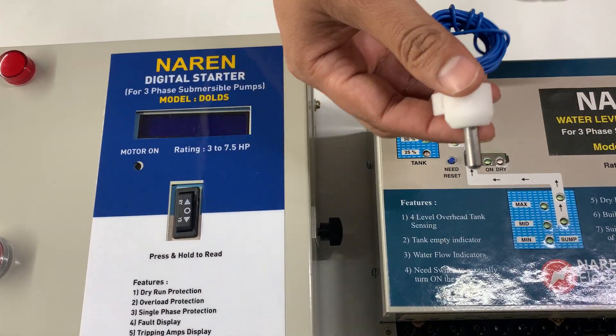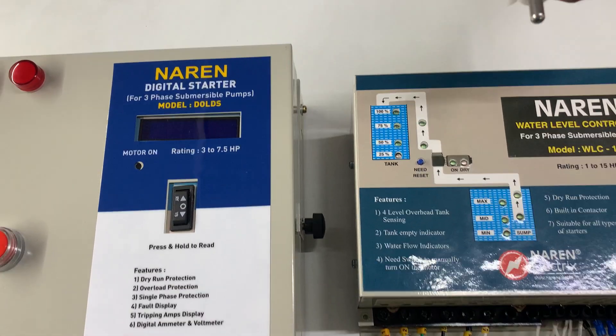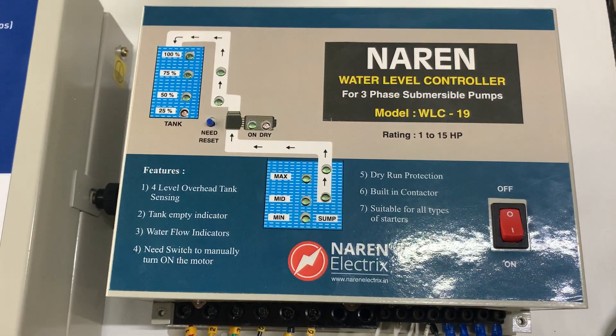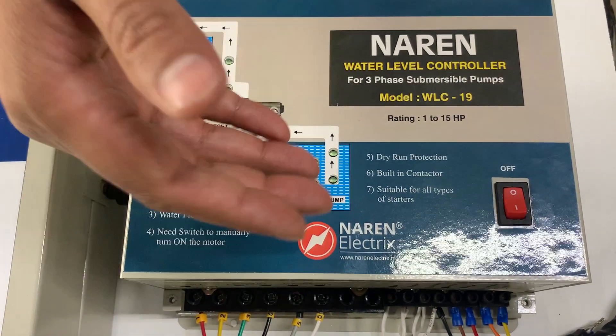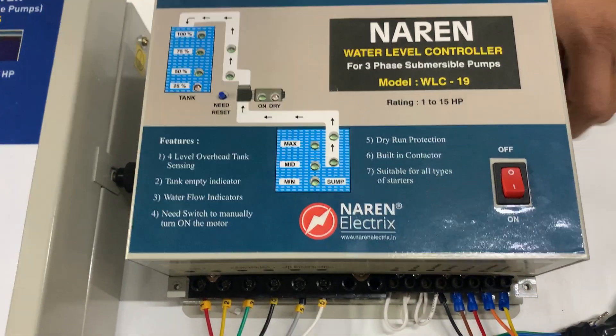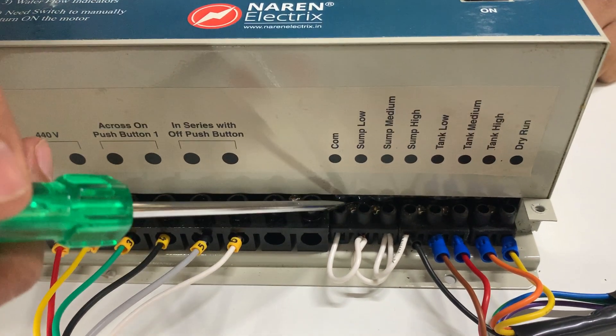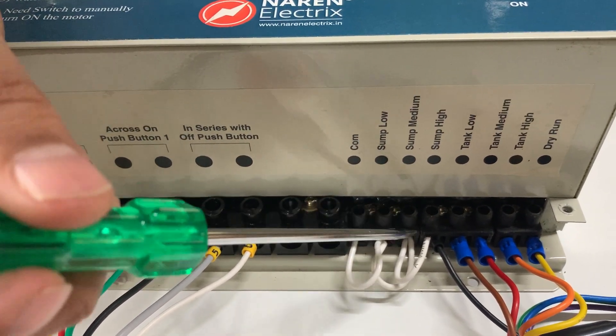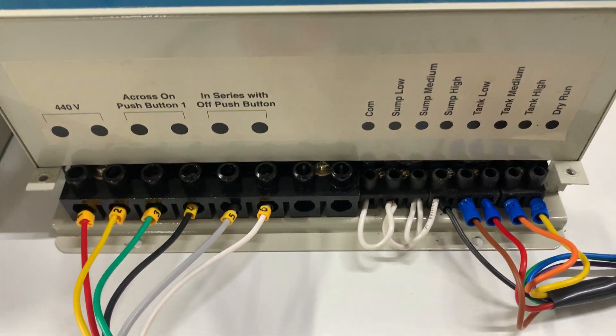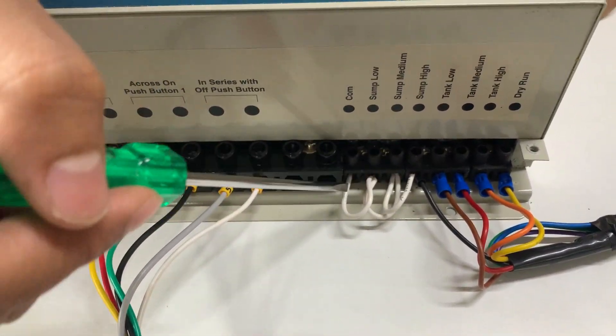Float sensors total eight in number. If you are using the borewell configuration, you need to short these terminals — the sensor connectors for the sump. All four sump terminals should be interconnected: common to sump low, sump low to sump medium, and sump medium to sump high. Once this is done, the controller will always assume there is water in the sump, which is the required setup for the borewell configuration.